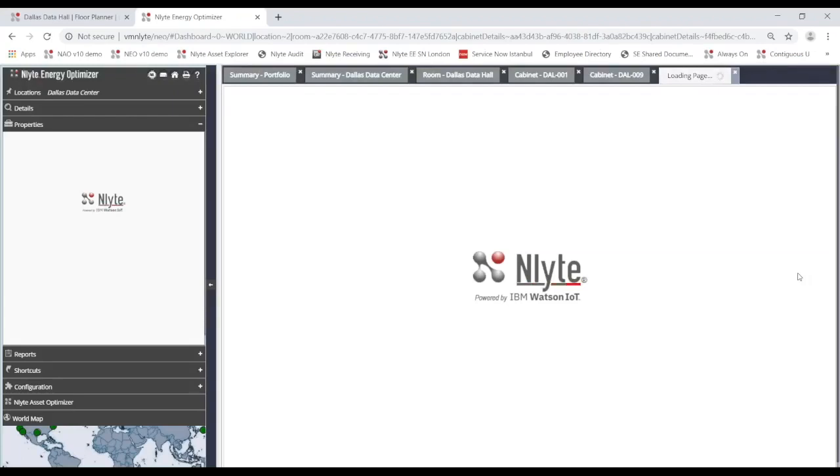Again, they're monitored very similar to the in-rack power strips, but they are capturing power at the tap-off that's being distributed to the servers inside of the rack. So again, three ways to look at the power distribution in the application: branch circuit monitoring, in-rack power strips, and then as soon as this loads, we'll take a look at the ability to see the in-rack, the busway.